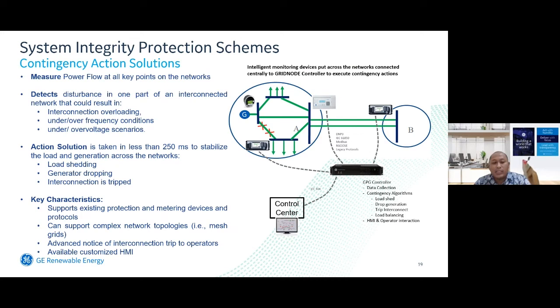And what are the key characteristics of this solution? It supports existing protection and metering devices and protocols. It can support complex network topologies. It has advanced notice of interconnection trip to the operator, and we also have a customized HMI. These intelligent monitoring devices are put across the network and connected centrally to the grid node controller to execute contingency action.